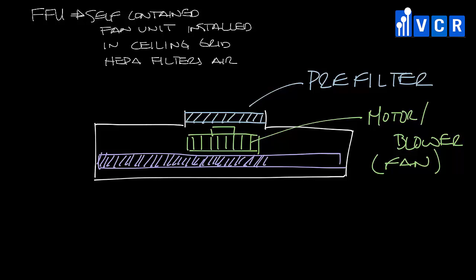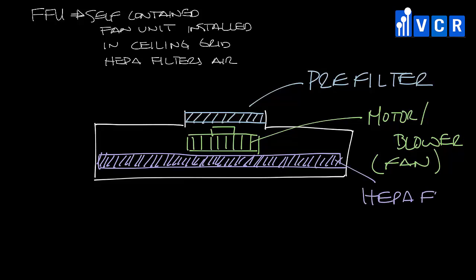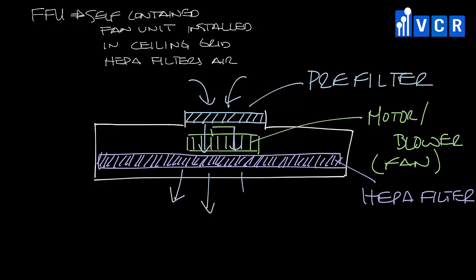In this case, this is open to the plenum. Air will be pulled in from the plenum through the pre-filter by the motor blower assembly, through the HEPA filter, and out the diffuser face into the space.